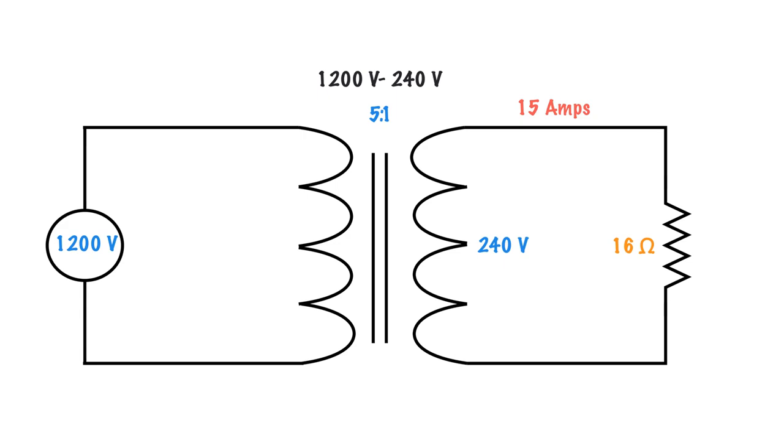Now this is where we can start using the turns ratio. We have 15 amps on the secondary and we have 240 volts on the secondary. We have 1200 volts in the primary. We need to remember that lower voltage means higher current, and higher voltage means lower current.